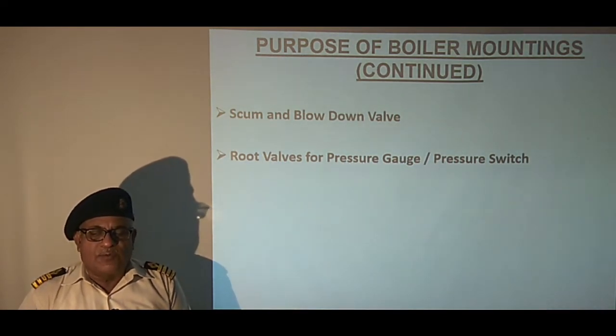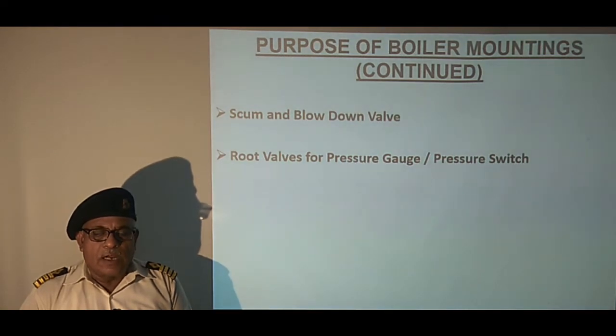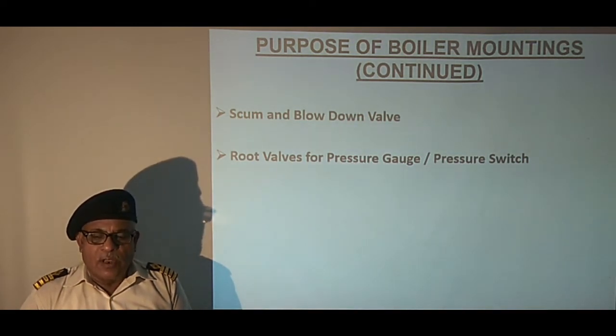Purpose of this valve is for connecting the pressure gauge at a convenient place and pressure switch for automatic start-stop of the boiler, combustion control, raising low pressure alarm and to trip the boiler at highest pressure below safety valve opening pressure.